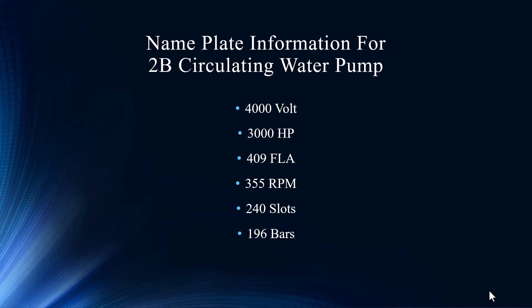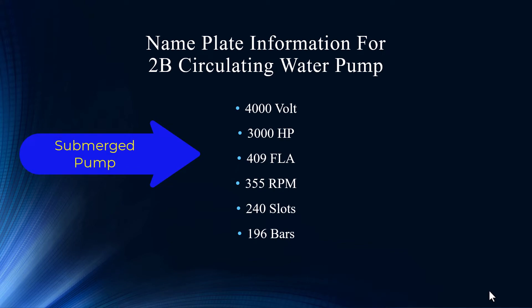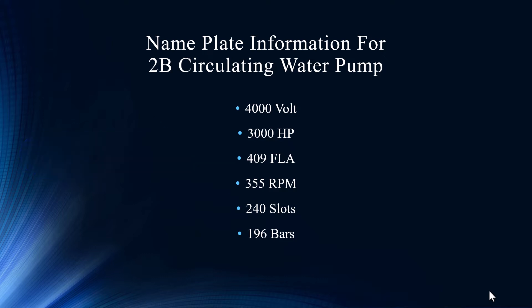The interesting thing about this motor is that it's in the river — you can't see it. This is a suction pump, a circ water pump, so it's sucking water out of the river, which is critical to utilities. This is a 4,000 volt, 355 RPM, 240 slots, 196 bars motor. It's a big motor underneath.